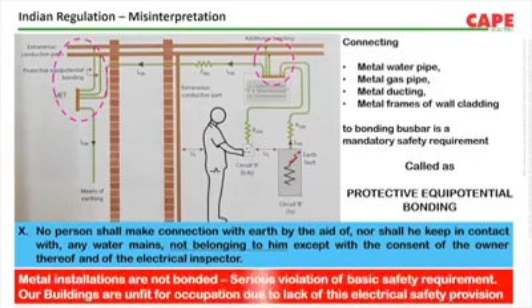As a result of misinterpretation of this particular regulation all over India, metal parts such as water pipe, gas pipe, ducting, and metal frames of wall cladding are not connected to the earth bus bar. For example, in large multi-storied buildings, there are firefighting water pipes for the water sprinkler system. These metal pipes are never connected to the earth bus bar. This is actually a clear violation of Indian rule, international rule and the CEA safety regulation. In European countries, if you make this violation, you can be sure that the building is unfit for occupation.